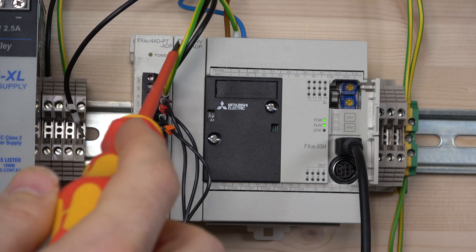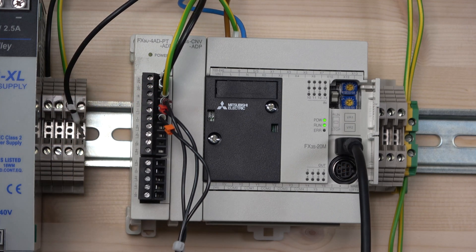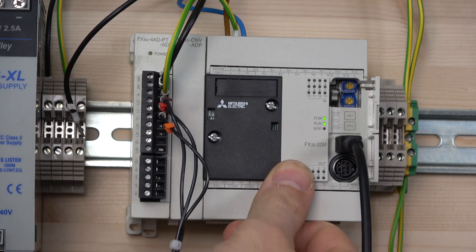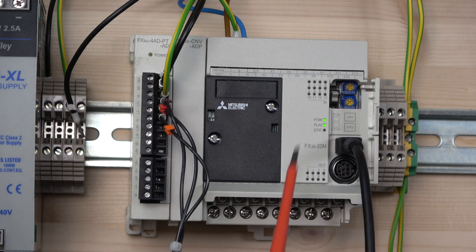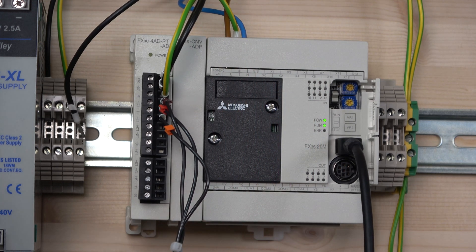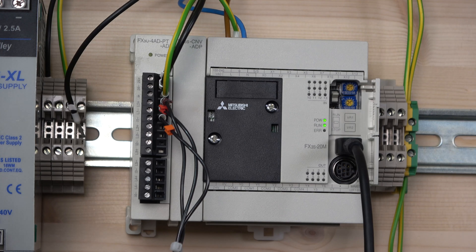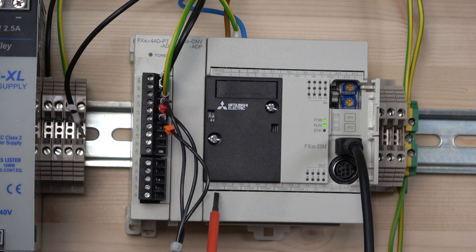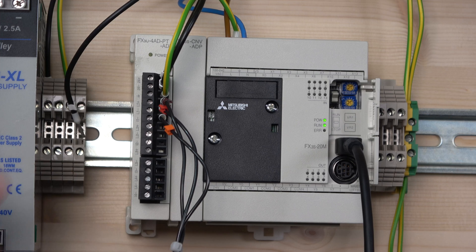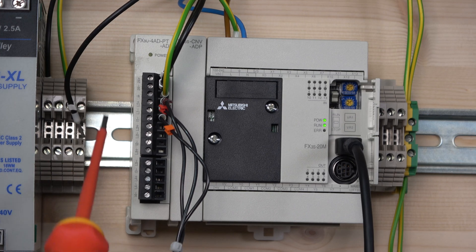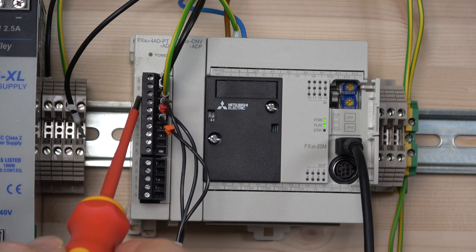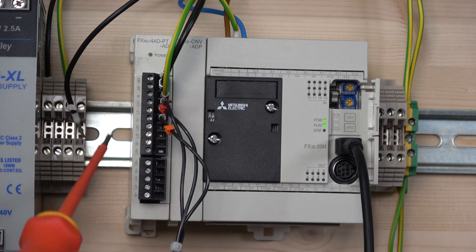Let's check out the actual terminals. It does need a separate 24 volt DC supply. If you don't want to use an additional DC supply, most Mitsubishi PLCs above a certain size have a 24 volt and 0 volt output you can use. You can see there's 24 volt and earth terminals.